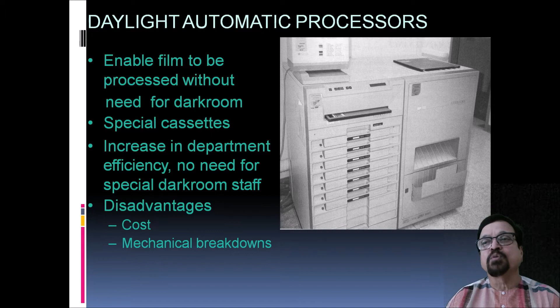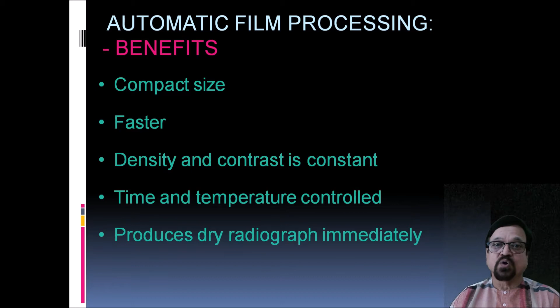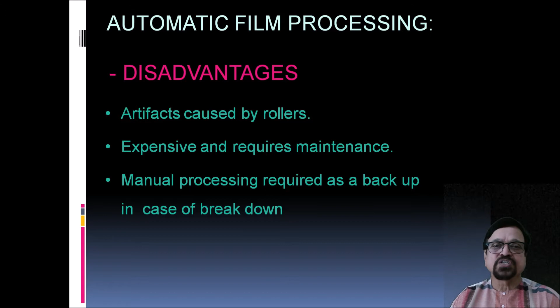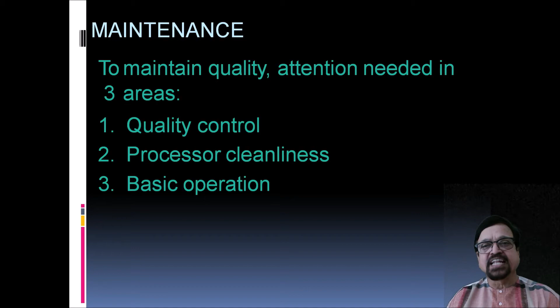So the automatic processor benefits: it is compact in size, faster, density and contrast are constant, time and temperature are controlled, and it produces a dry radiograph immediately, which can be either dispatched, stored or reported. Now, automatic processing disadvantages. What are the disadvantages? Artifacts caused by the rollers. It is expensive and requires maintenance. Manual processing is required as a backup in case of breakdown. So you need more maintenance cost and face frequent breakdowns. Now, maintenance: to maintain quality, we concentrate on the following three areas: quality control, processor cleanliness and basic operations.